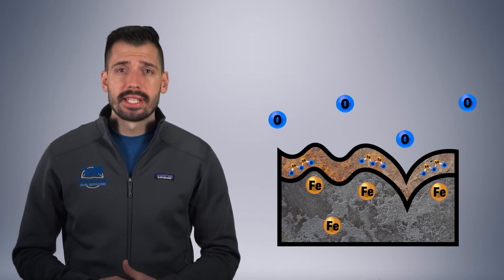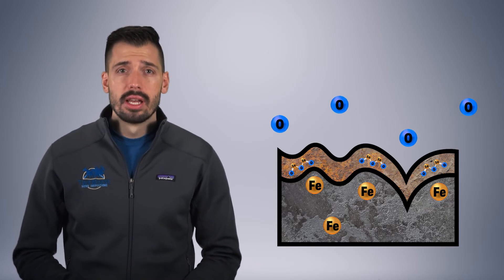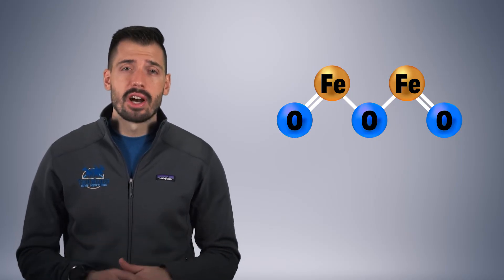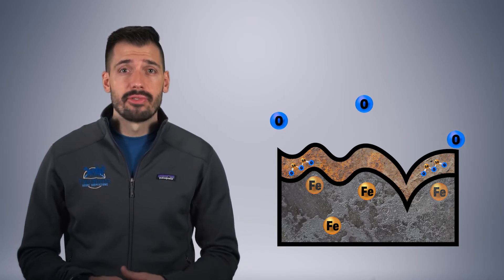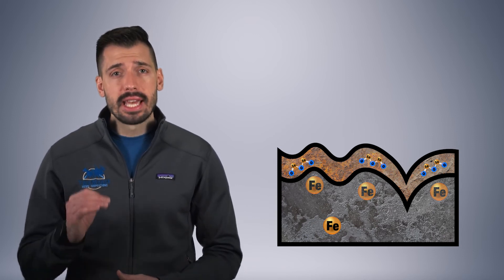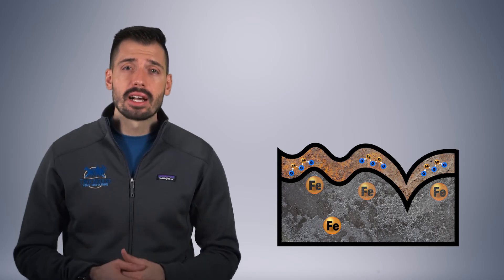With that said, corrosion is expected, and in a closed loop system, the limited amount of oxygen trapped inside the pipes will create a very fine layer of rust known as iron oxide. This oxide layer will form a protective layer of rust on all the ferrous parts of the system, preventing stray oxygen atoms from causing ongoing corrosion. Iron oxide is created any time that three oxygen atoms bind with two iron atoms. There are 16 types of oxides that could be produced, but we'll just call this type of oxide rust. And if no additional oxygen is added to the system, all the oxygen atoms in the system will find an iron atom and create rust together. The layer of sacrificial iron oxide is expected, and it will protect the rest of the ferrous materials by absorbing all the oxygen atoms and converting them into rust until the closed system is completely oxygen free.